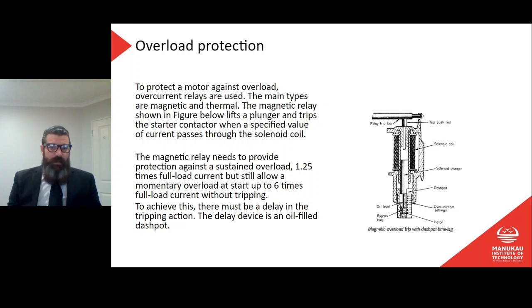The magnetic relay needs to provide protection against a sustained overload, 1.25 times the full load current, but still allow a momentary overload to start up at 6 times full load current without tripping. So that's our start current, remember. To achieve this, there must be a delay in the tripping action. The delay device is an oil-filled dash pot. Don't ask me what a dash pot is, I don't know the answer.